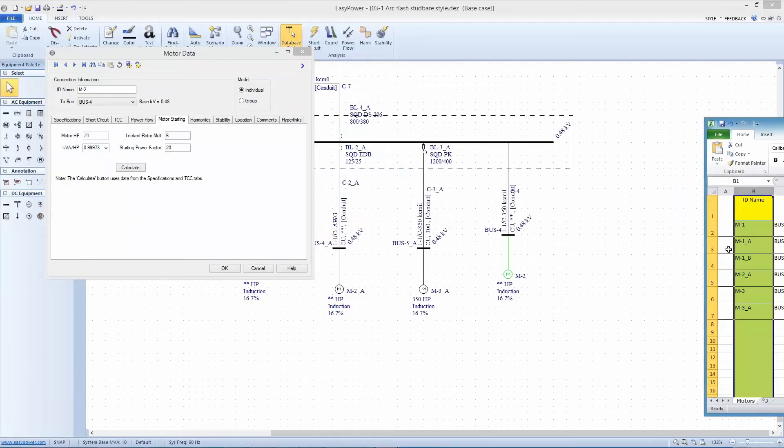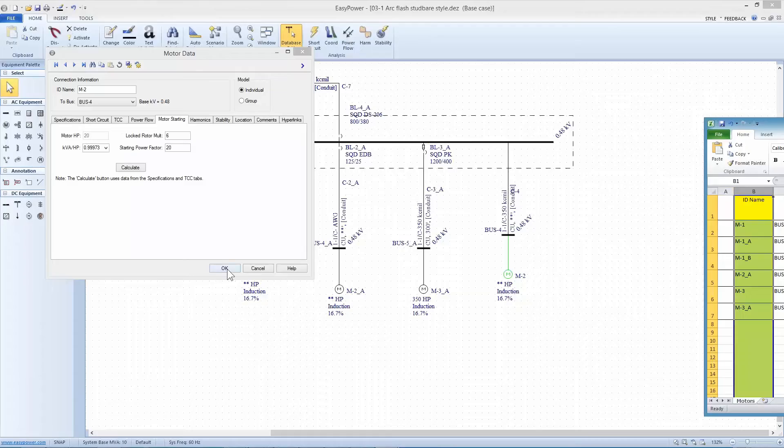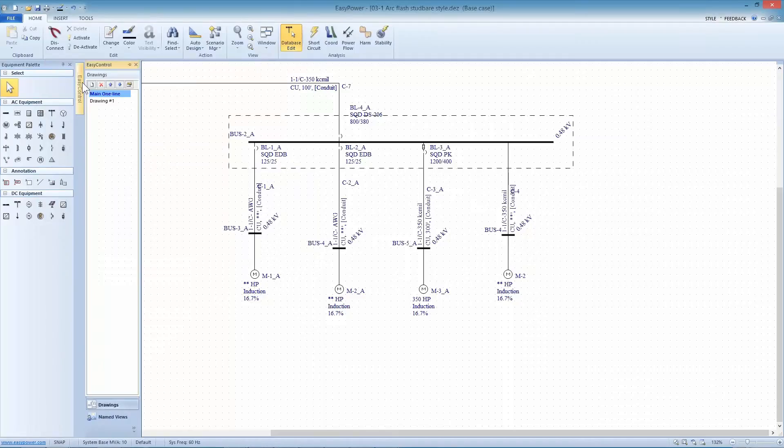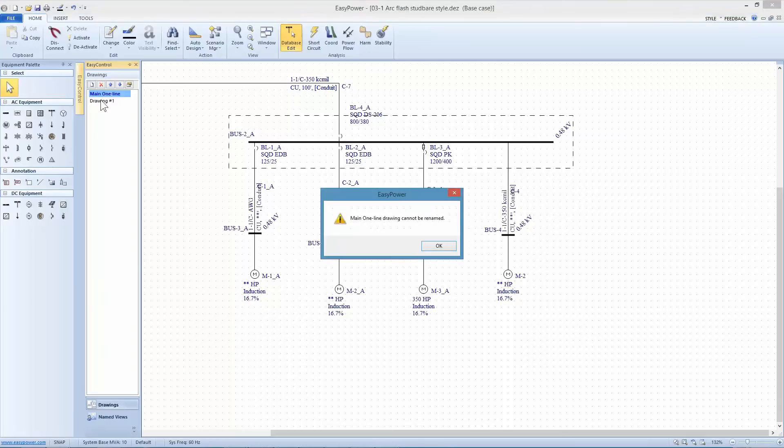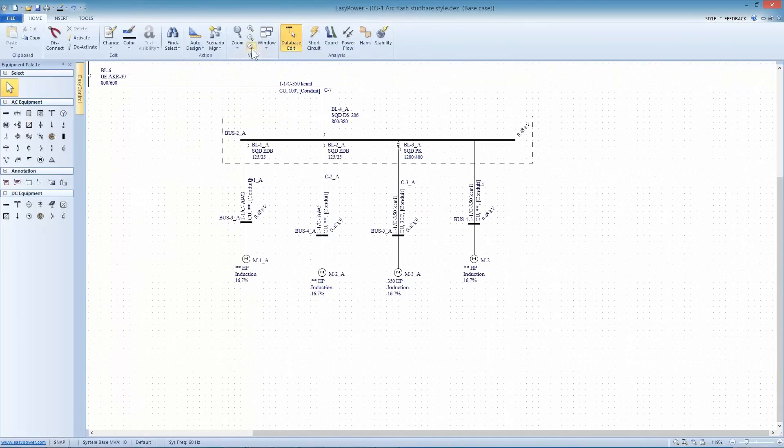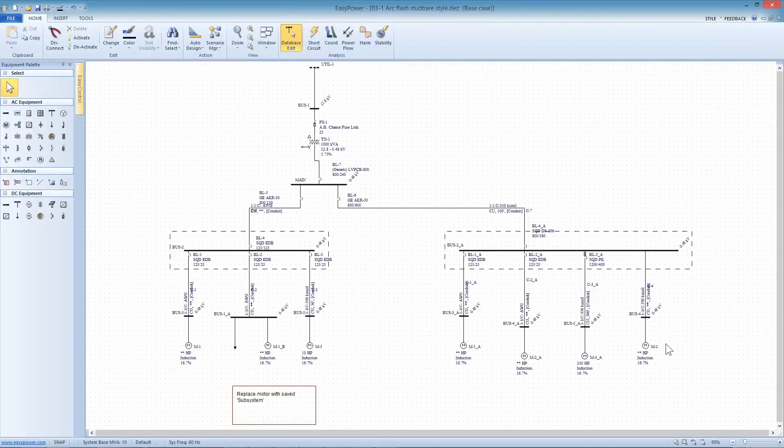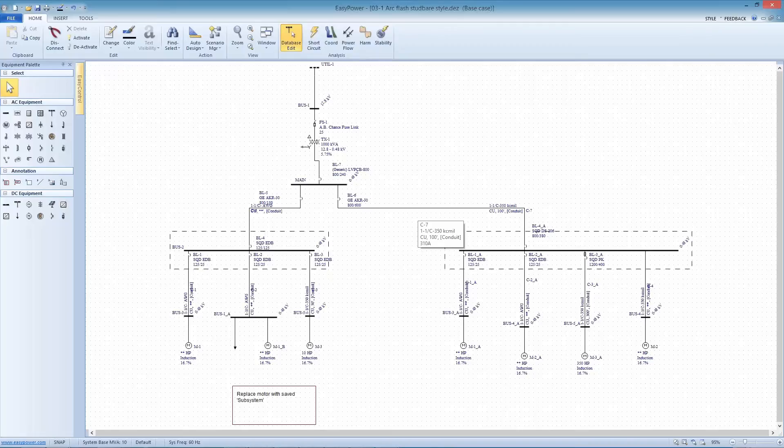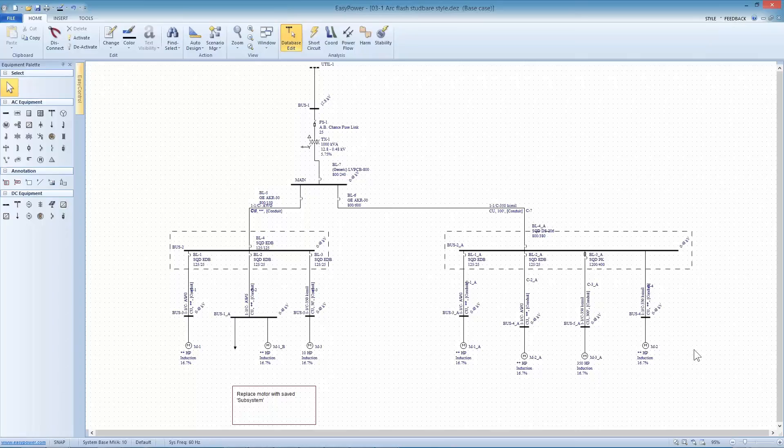My point is, literally every subsystem that I can isolate in my one-line, I can build up a chart for and methodically go out and organize data collection for my one-line. And at this point, what I've done is essentially just the one sub-feeder. I want to go back and enter that data and then verify that it will produce the results I want. That's a step down the road in modeling. But the point I want to make is the templates for the data collection are relatively simple if you can start with a skeleton one-line diagram. And that can be done with EasyPower or a one-line designer. And you're off and running.